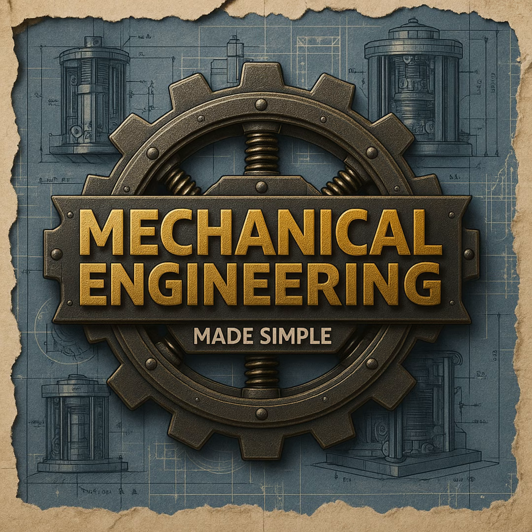Many operators make that exact assumption, and honestly, it often leads to catastrophic failure. Wait, really? Why? Because heavy industrial machines do not magically heal themselves. A lower amplitude simply means the forcing function has changed. It does not mean the mechanical condition has improved. Wow. Okay, so if the machine isn't healing, what is physically making the vibration drop? It usually points to an external variable, like maybe a variation in the fluid load being pushed through the pump, or a shift in the plant's operating temperature or ambient pressure.